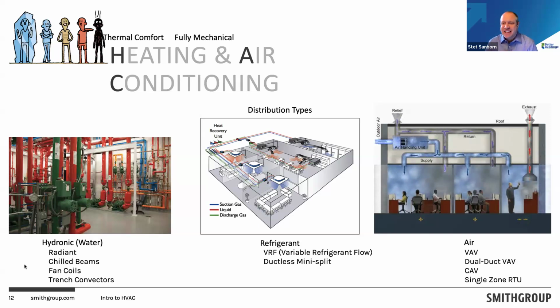So I did want to add just a couple of the words that you might hear out in the industry that might lead you to understand which types of this distribution you have in case you don't know in your portfolio. So if you have a hydronic system, water-based system, it likely will be paired with maybe radiant heating, radiant cooling, chilled beams, hydronic fan coils, trench convectors, baseboard radiators. There's kind of a lot of that technology that's all water-based. And depending on what climate zone you're in, you might have more likelihood to have one of those distribution methods.